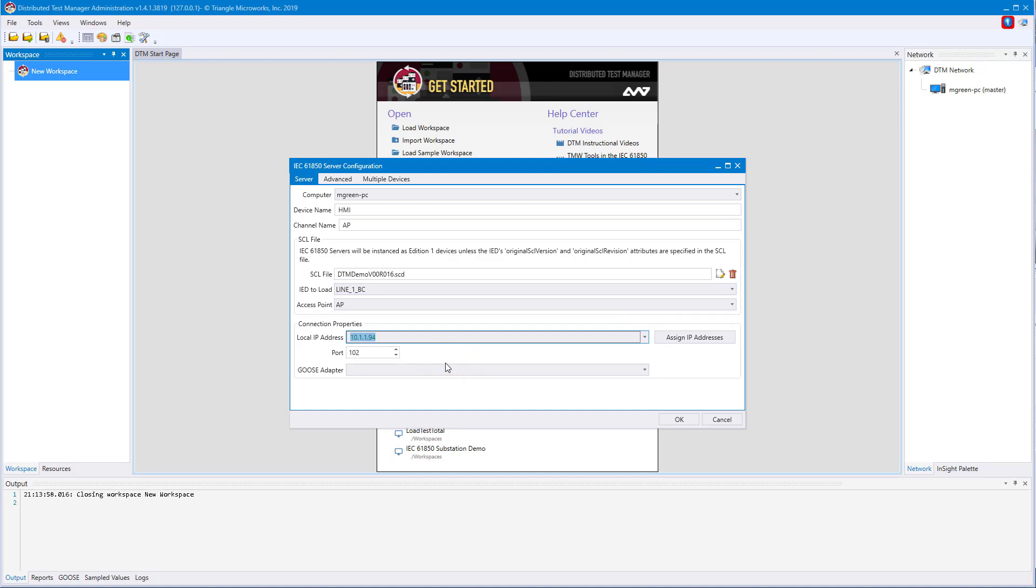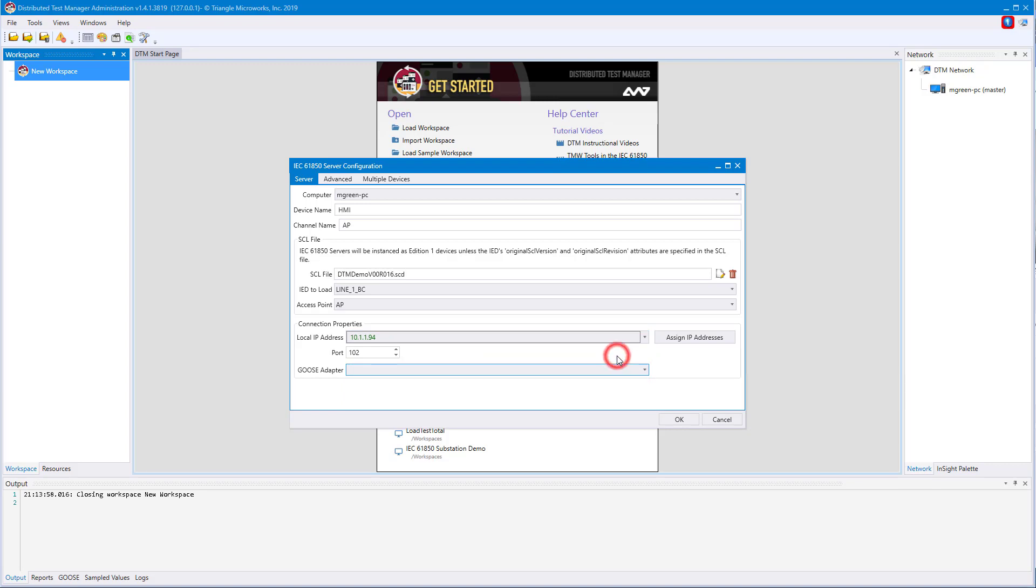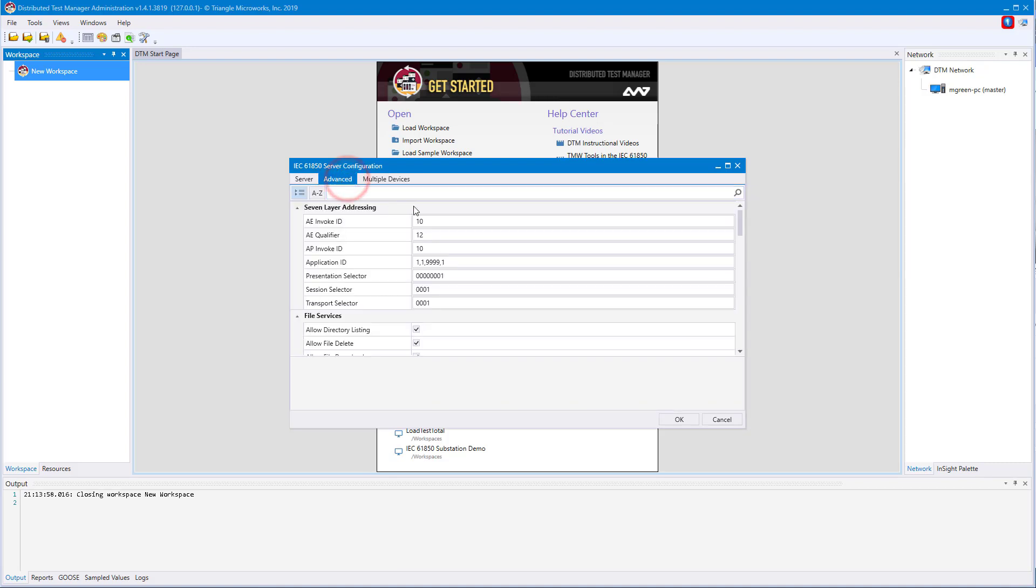If your device needs GOOSE, you can select the GOOSE adapter here. You can also add IP addresses to your network adapters, but that will be shown in a different video. The Advanced tab is similar to the one shown in DNP. This is where protocol-specific configurations are updated. This is also where you'll find sampled values adapters if your device needs to have access to sampled values.